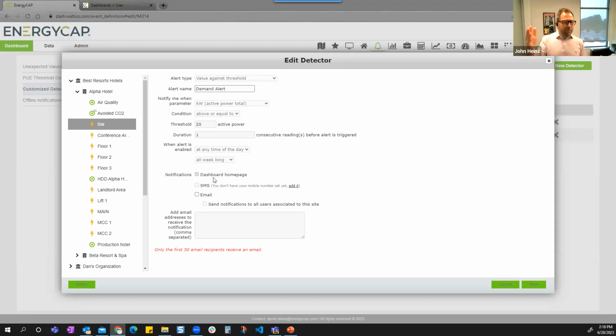You would not want your systems operating at full capacity on a Saturday if you're supposed to be shut down. So you can automatically have the system send whoever you want text messages saying, hey, wait a minute, the building systems are turning on during a weekend, we're supposed to be shut down. Really helpful in that case, so you can go into your control systems and dial things back, because if you're operating at full capacity with no one there, you're just wasting energy, and it could potentially be a hot day with a demand spike when no one's even in the building.